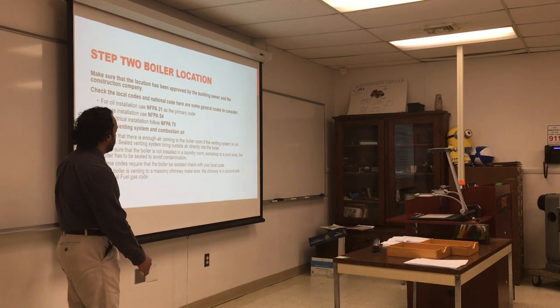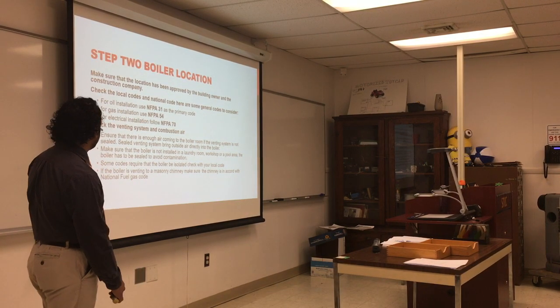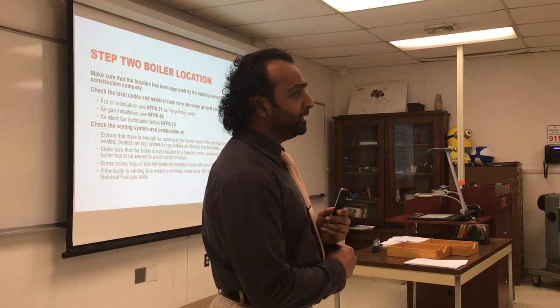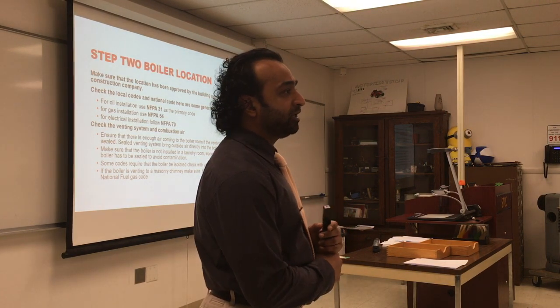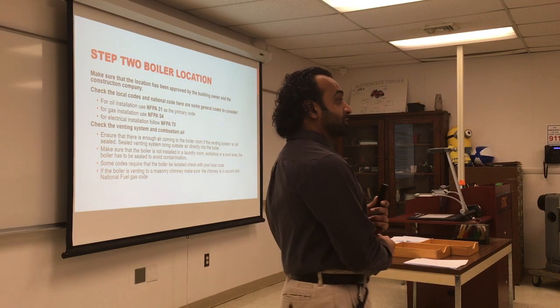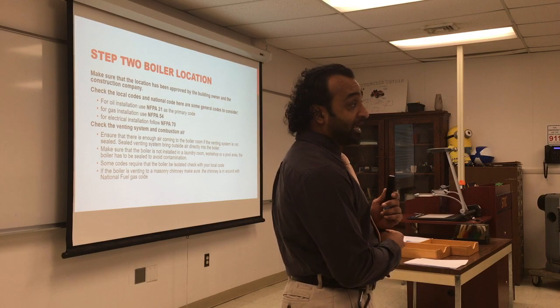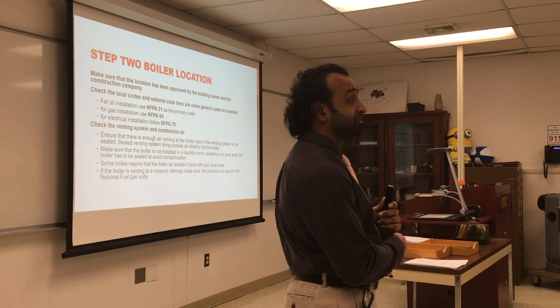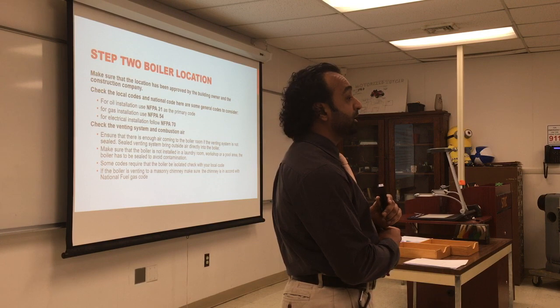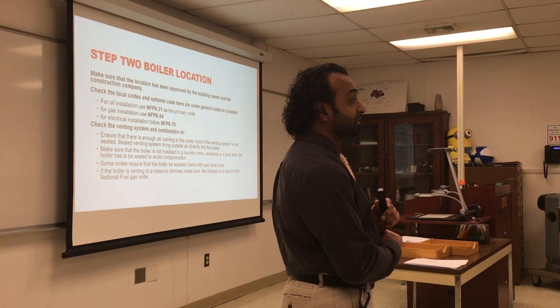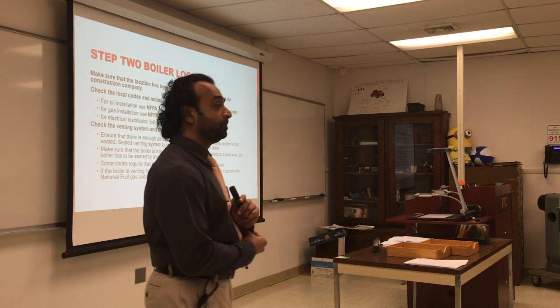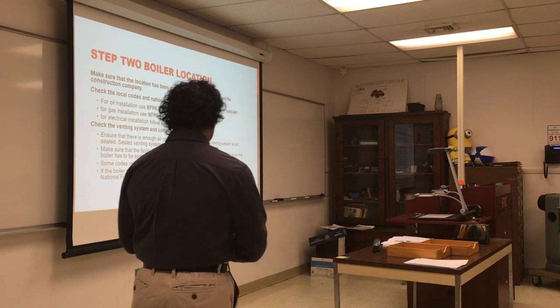If the boiler is venting into a masonry chimney, make sure the chimney is in accord with the National Fuel Gas Code — that means it has enough venting capability and is not too long. If the chimney is too long, it will backdraft. The solution is a sealed construction with an opening just for that boiler — you'll probably need to put a hole in the wall for that.